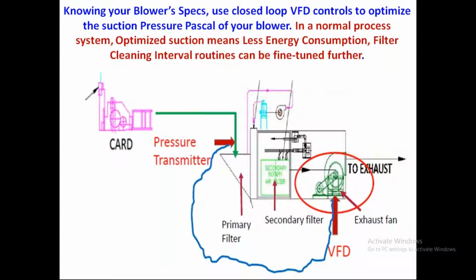Coming to the system, it is a closed loop control system, especially on a waste collection blower in a textile mill. The blower, or the carding machine, needs only 600 Pascal. The header can be maintained at 800 Pascal. And you can see the primary filter and the secondary filter. This exhaust blower is sucking the air from the equipment and throwing it to the atmosphere. Here you find the suction pressure, the negative pressure kept at the carding machine, is only 600, whereas the exhaust fan is operating at 2200 Pascal. This is a big loss. The transmission or distribution loss is so big. How can this be corrected?